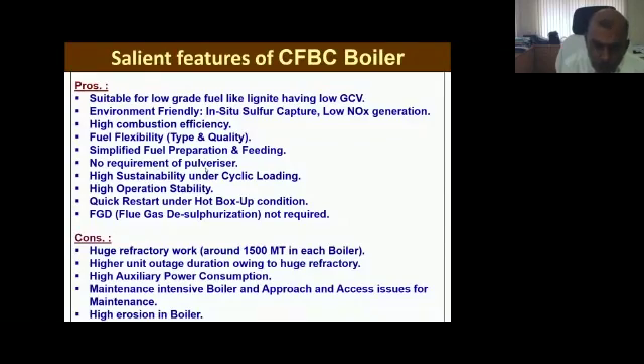Because when there is an outage, the unit outage duration is higher owing to the huge refractory. Whether it is a planned outage or a forced outage, in case of a forced outage, almost 24 to 36 hours is lost only in cooling the boiler with the improvised operational practice. Otherwise, earlier it used to take more than 72 hours. Even if there are some issues in the cyclone or backpass side, which is a high temperature zone, the outage time will be say 60 to 70 hours without doing any work. And then only you can start the maintenance activity. So this is a major disadvantage.